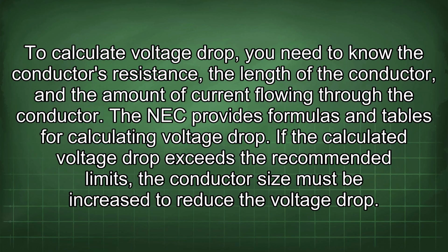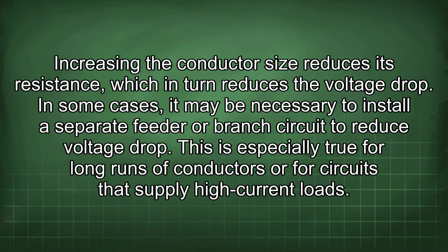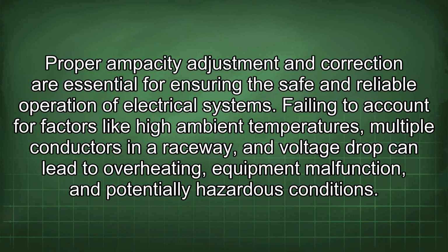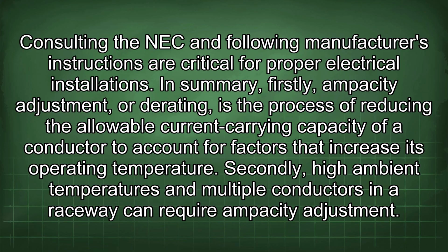If the calculated voltage drop exceeds the recommended limits, the conductor size must be increased to reduce the voltage drop. Increasing the conductor size reduces its resistance, which in turn reduces the voltage drop. In some cases, it may be necessary to install a separate feeder or branch circuit to reduce voltage drop. This is especially true for long runs of conductors or for circuits that supply high current loads. Proper ampacity adjustment and correction are essential for ensuring the safe and reliable operation of electrical systems. Failing to account for factors like high ambient temperatures, multiple conductors in a raceway, and voltage drop can lead to overheating, equipment malfunction, and potentially hazardous conditions. Consulting the NEC and following manufacturer's instructions are critical for proper electrical installations.